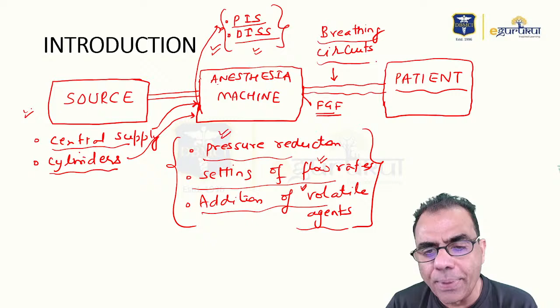The three most important things, which we have already seen, that happen in the anesthesia machine are: pressure gets reduced, we set the flow rates, and we add the volatile agent. And another very important thing about the anesthesia machine is that it has a safety mechanism, the pin index system and diameter index safety system, which ensures that wrong gases are not delivered to the patient. Now the gases from the anesthesia machine are called fresh gas flow. This fresh gas flow will be delivered to the patient through breathing circuits, breathing tubes.